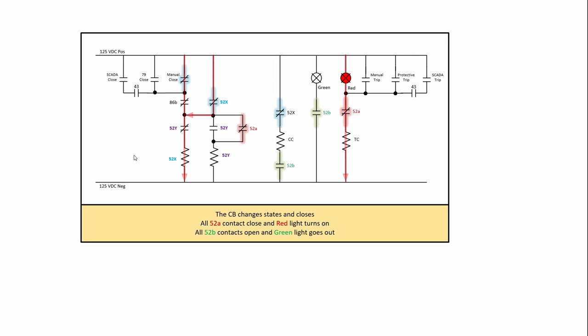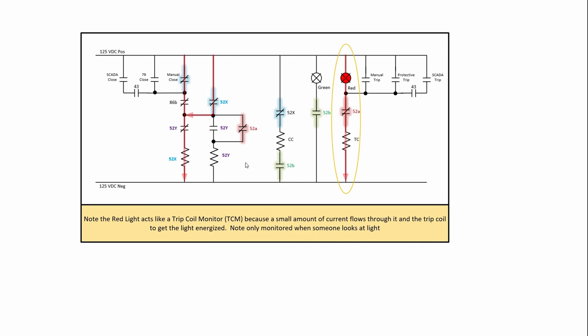Once the closed coil has been energized, it changes states. That's going to have the 52As all closed and the 52Bs open. It shuts off the green light, turns on the red light, and it then is going to ultimately pick up that 52Y. Note here that the red light also serves as a trip coil monitor because there's a little bit of current that flows through that, not enough to trip it. So don't think that that trip coil is being energized because that's a high impedance. So we've got a little trickle current going through there. And we can use that as a trip coil monitor. The problem is you only get to use it as a trip coil monitor when you're looking at it.